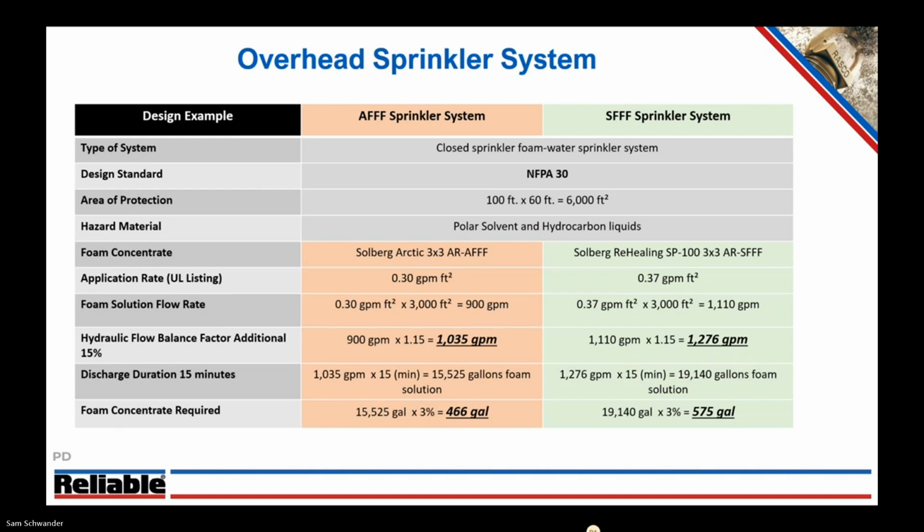So I think some folks get confused. They're like, look, we're just going to drain the tank out and fill it back up with the environmentally more friendly concentrate. It doesn't necessarily work that way.